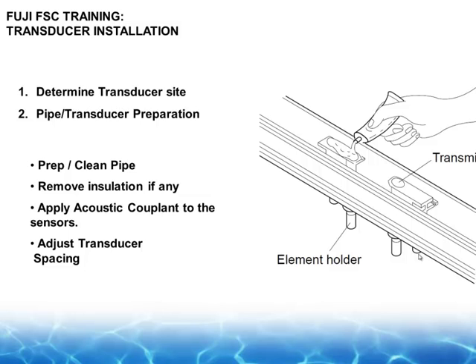Sensor's flat, pipe is round. We have multiple different flavors of grease. My favorite is a silicone grease because it's viscous, doesn't care about moisture, it doesn't care too much about most temperatures, and it does a better job. Some brands have water-soluble grease, which are great. If you get wet on the pipe, or get some heat on the pipe, they don't stay on the pipe. The only drawback with the silicone grease is, if you have a pretty pipe, you'll never paint that spot again, no matter how much you clean it.